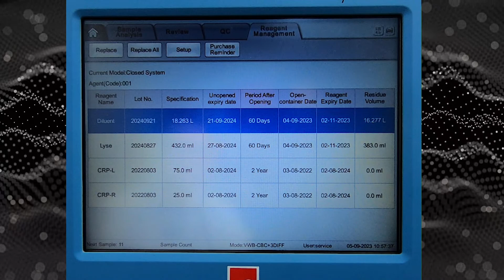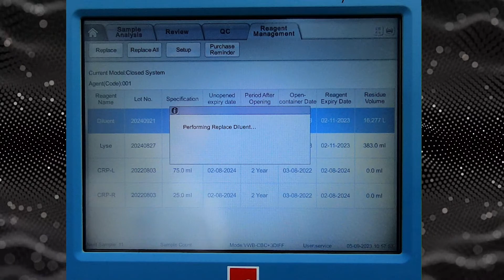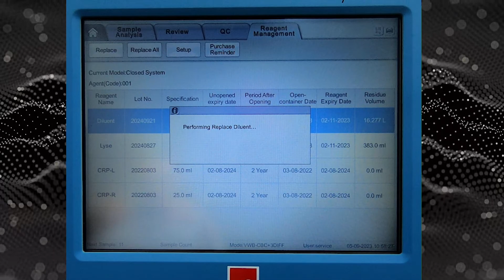When we go to home, okay, right now we have a short break because by mistake I pressed the replace button, right? Replace diluent. So the analyzer is replacing diluent. On the top, we also have replace all, just in case we want to replace all reagents at the same time. Usually the consumption of reagents is not equal, so it is not necessary to replace all reagents at the same time. Usually you will replace diluent, lyse, or CRP reagents separately. Each one will be replaced separately.